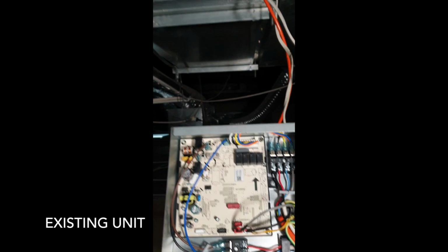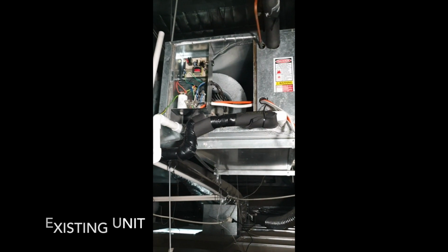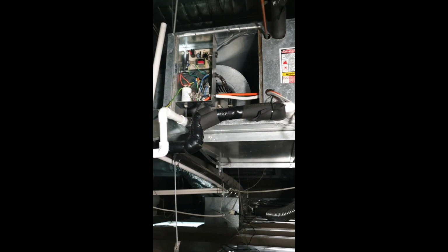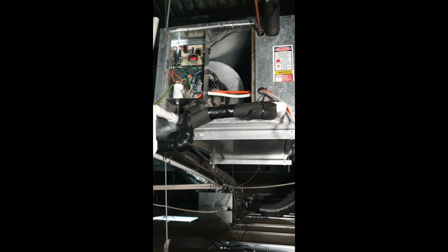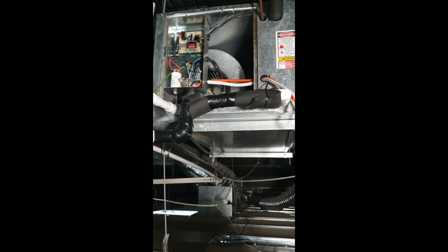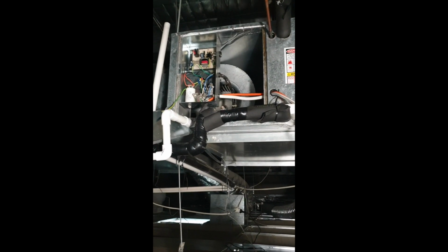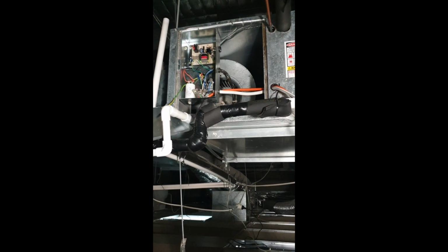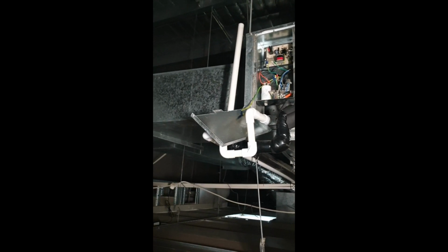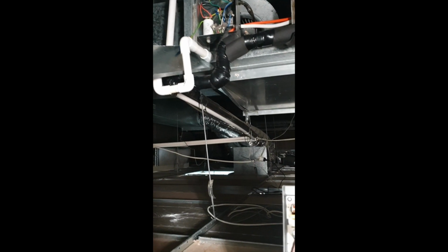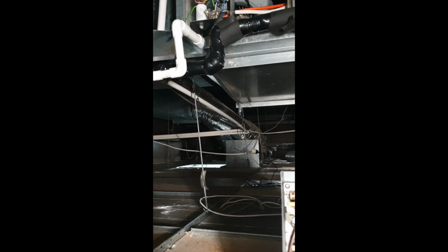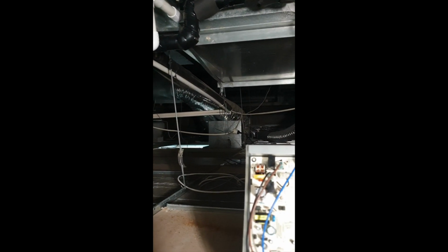Hi guys, we're in the ceiling space now, replacing an existing 18 kilowatt R22 ducted split system with the Polaris Intelligent Series. As you can see here, we're looking at the indoor unit, which is not requiring replacement, including transitions for ductwork and that messy, horrible work of actually pulling a fan coil from an occupied office. We also don't need to replace the pipe work that we can see going away in the distance here, so there's no interruption to the occupants of this building.